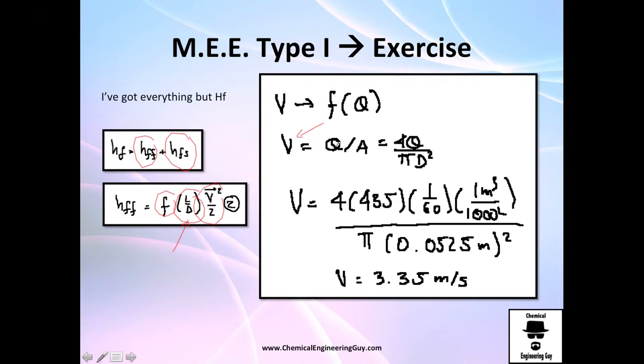I need to find out the velocity. I do it from this equation, Q divided by A. I just substitute data, the volumetric flow rate, change it to seconds from minutes and cubic meters from liters, so I have international units, and I got 3.35 meters per second is the velocity.